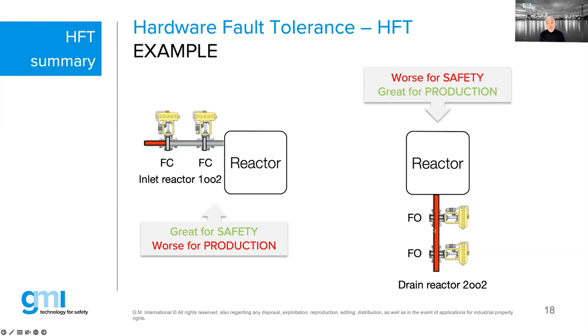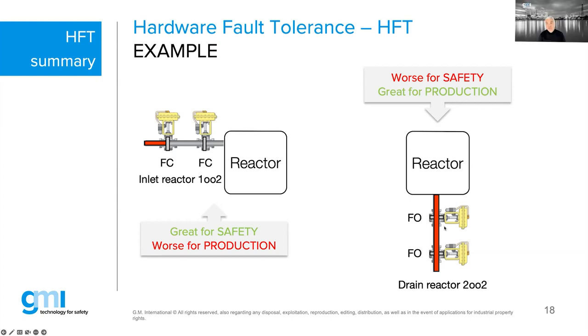On the right-hand side is the opposite: two fail-open valves in a drain function. A second valve is added because if the first leaks, you lose expensive product. However, since both valves need to be open, we have no safety redundancy — if one valve is stuck closed, you cannot drain. This is a 2oo2 configuration: great for production availability, but no dangerous fault tolerance.